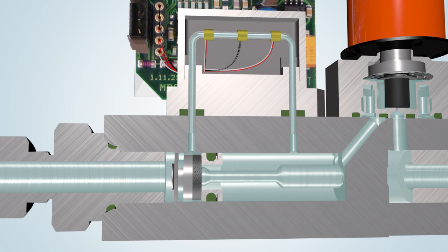Once the instrument has been connected to the process line, the pre-pressure can be set. The body and the sensor are now filled with gas.